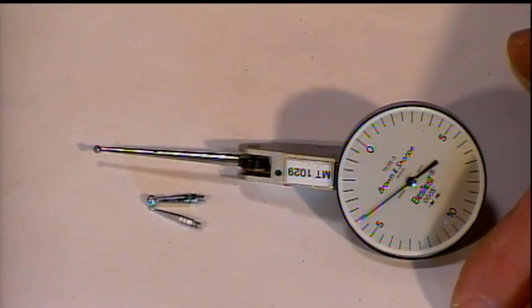Is that a common thing where people go, oh, I need a longer reach or a shorter reach, and they just swap out the contacts? It is. I'll see an indicator box that has a 5-inch long tip and a 1/2-inch long tip, and I know they're not getting linear readings. I understand they need them for certain jobs, but you have to have an indicator made for that contact point.